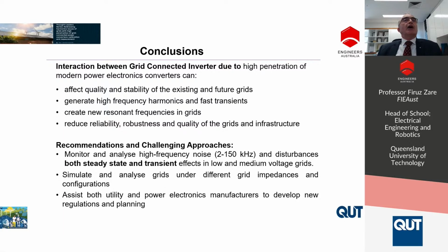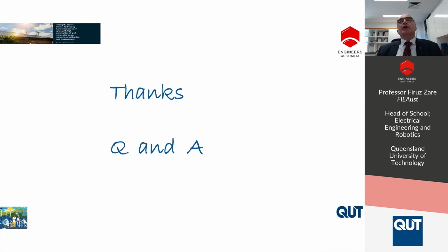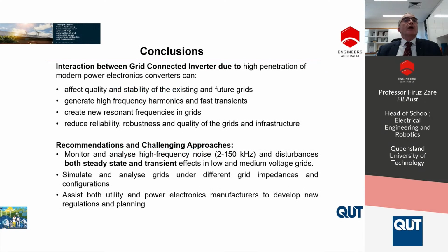Having said that, I do believe it's important to monitor and analyze high-frequency harmonics above 2 kilohertz. The main point is that when we are talking about these harmonics, we are not talking about below 2 kilohertz. We are talking about high frequency, which is one of the emerging issues. I believe those systems are important to be analyzed in terms of simulation and analysis, and we need to work with utility and power companies to manage the level of the harmonics.